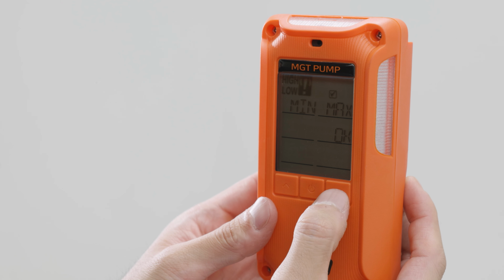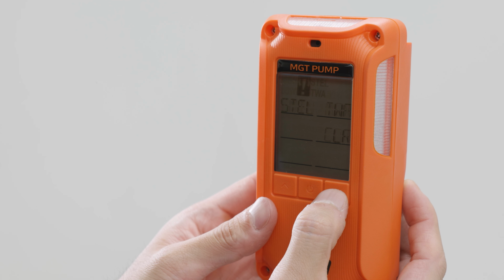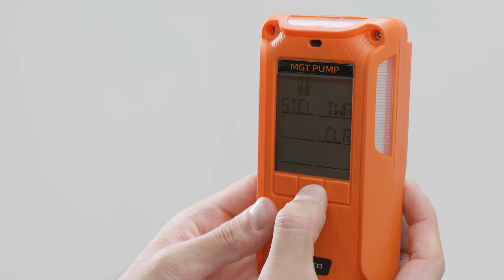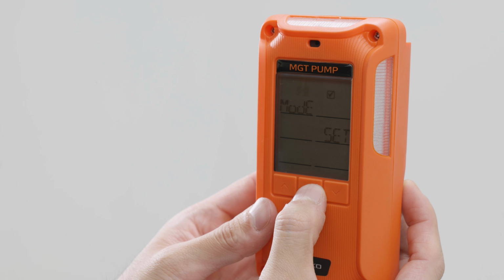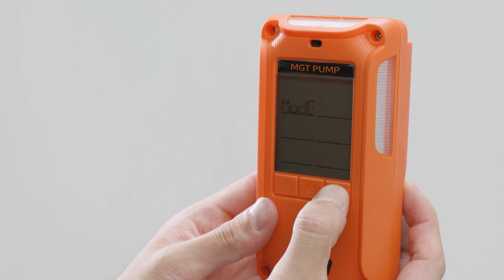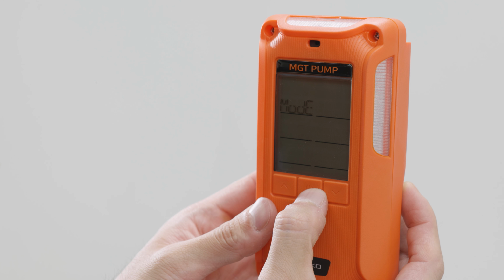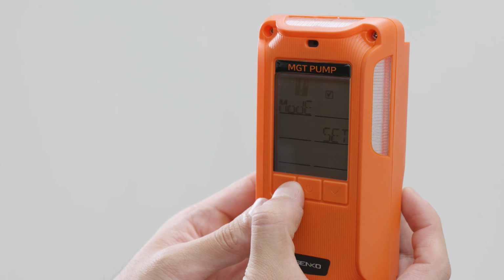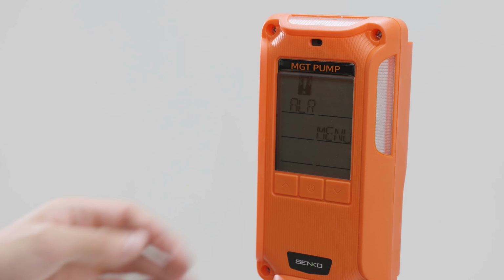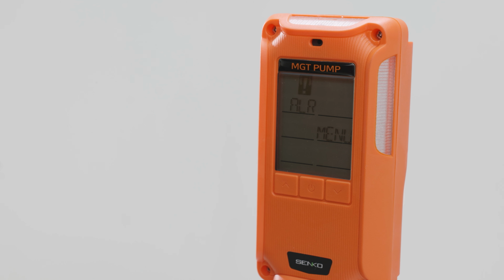In Auto mode, the alarm stops automatically when gas concentrations return to safe levels. In Latch mode, the alarm remains active and the peak value is held until it is cleared manually. After selecting the desired mode, press the Select button to save. After saving your settings, you can press the Select button once to go back to the previous screen.